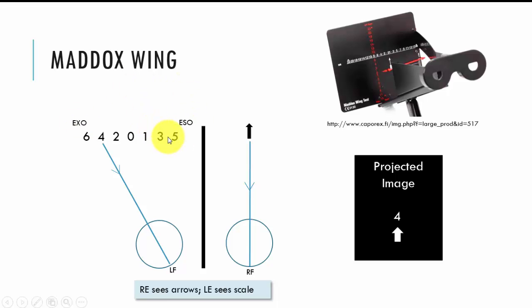However, some patients will tell you it's pointing to the four if it falls between here, the three and the five. And so what you need to clarify with your patient when using the Maddox wing is, is it actually pointing to the four or is it between the three and the five. So make sure you ask that question because it is the difference between documenting that the patient has an exo versus an eso, and that's important in terms of measuring the size of the deviation.